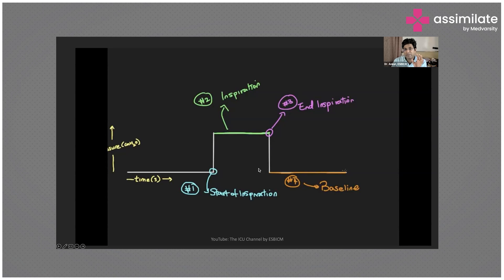The terminology: the thing which triggers the ventilator — which tells the ventilator that you need to start the inspiration — is called your trigger. There are different types of triggers. The thing which tells the ventilator to stop the inspiration so that exhalation can take place is called the cycle. These two terms are important.